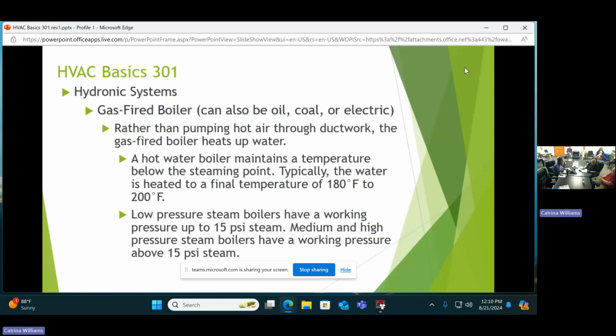But once that steam goes through your system, you can recover that many BTU. So you can see the big difference of how much more heat steam can give us versus hot water. 970 BTU at that particular point to get water to steam because you're changing state. That's the latent heat we were talking about the last couple days.